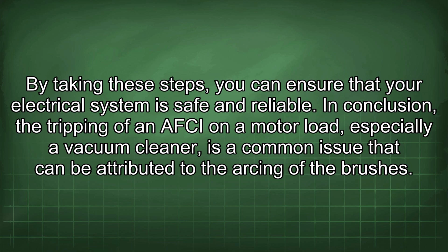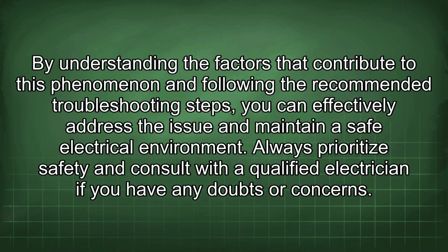In conclusion, the tripping of an AFCI on a motor load, especially a vacuum cleaner, is a common issue that can be attributed to the arcing of the brushes. By understanding the factors that contribute to this phenomenon and following the recommended troubleshooting steps, you can effectively address the issue and maintain a safe electrical environment. Always prioritize safety and consult with a qualified electrician if you have any doubts or concerns.